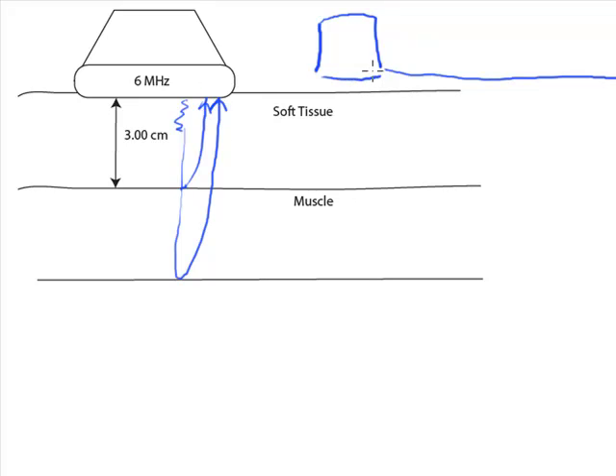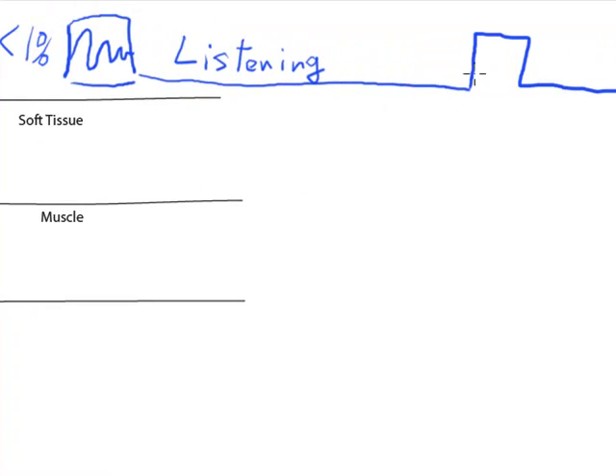So really it turns out that it's only on typically less than 1% of the time. It's actually producing sound, and the rest of the time it spends listening for the echoes to return. And so the pulse in here, something like that, and then over here it emits another pulse. So if we just draw the pulses, it would be like that, and then it's not making any sound for a long time, and then it generates another pulse of sound. So that's called pulsed ultrasound.